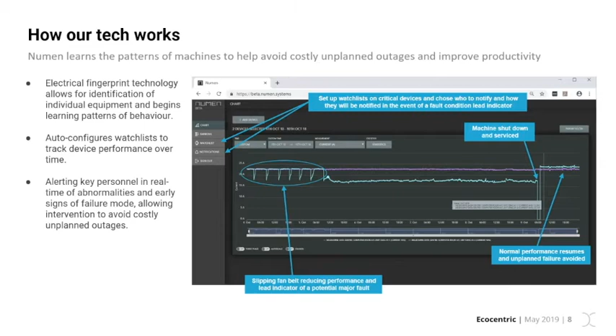On the far right-hand side of that graph, the normal line is above the purple one, and the abnormals are the rest of it. So really, it was just by chance this particular fault turned up the day we installed it. We don't know how long it was slipping for, but the company that has this loved it and thought this is great. So by knowing what happens and isolating anomalies, we can alert key personnel on a site to potential problems, and that fits into the preventative maintenance category.